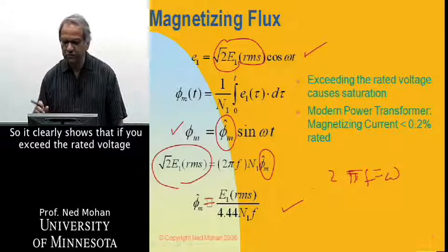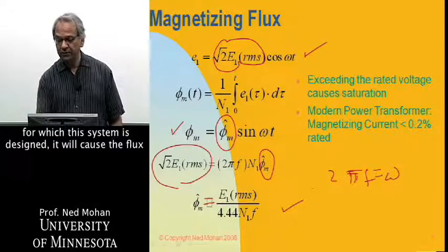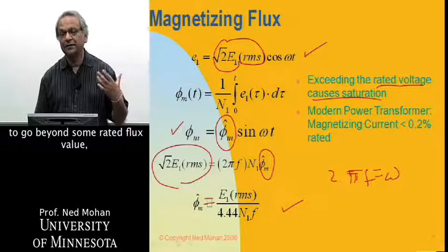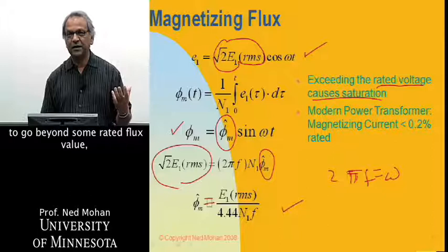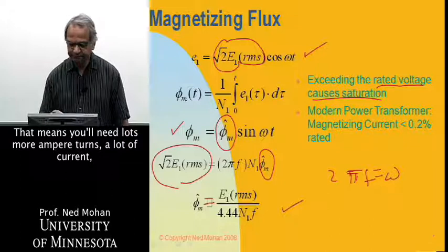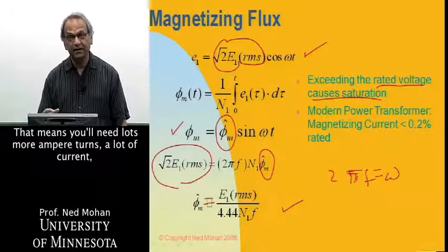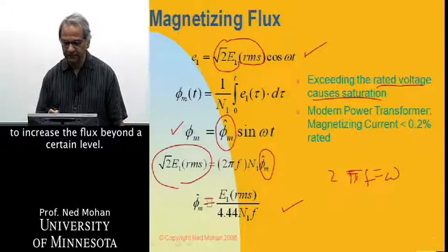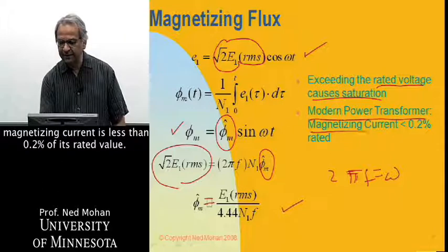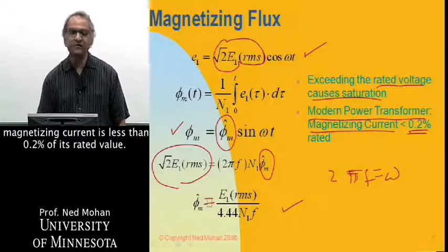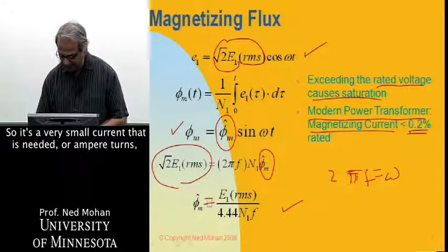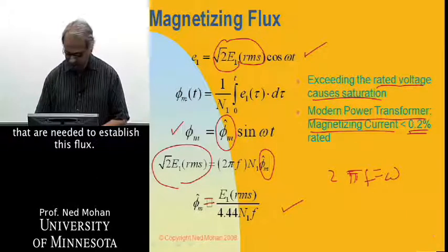This clearly shows that if you exceed the rated voltage for which this system is designed, it will cause the flux to go beyond some rated flux value, and this whole thing will saturate — meaning you will need a lot more ampere-turns, a lot of current to increase the flux beyond a certain level. In modern power transformers, magnetizing current is less than 0.2% of its rated value, so it's a very small current needed to establish this flux.